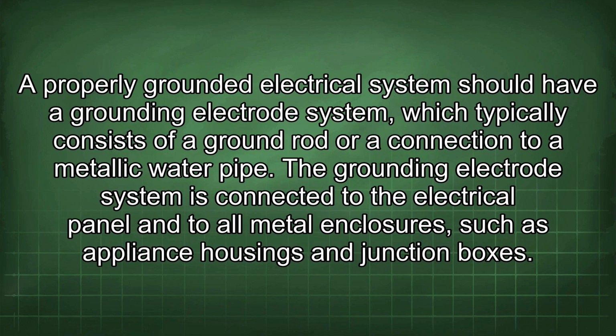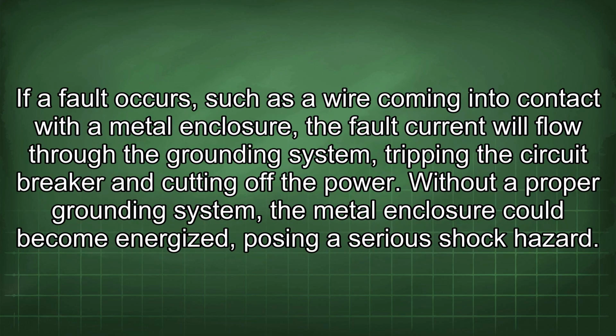The grounding electrode system is connected to the electrical panel and to all metal enclosures, such as appliance housings and junction boxes. If a fault occurs, such as a wire coming into contact with a metal enclosure, the fault current will flow through the grounding system, tripping the circuit breaker and cutting off power. Without a proper grounding system, the metal enclosure could become energized, posing a serious shock hazard.